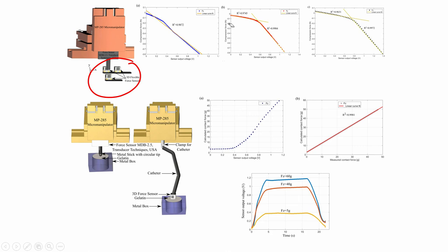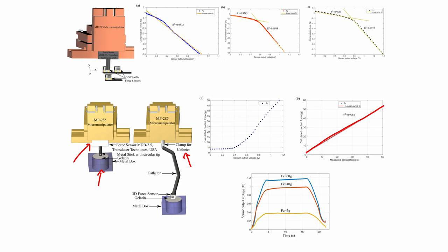Instead of measuring resistance directly, a potential divider or Wheatstone bridge gives the voltage change. Applying a known force reveals the output voltage, allowing calibration of the fabricated sensor. This is a very important experiment — whenever you fabricate any sensor you must calibrate it against a commercial sensor. For tissue testing, phantom tissue is used first: a gelatin-filled metal box acts as the phantom. Pressing the catheter onto the gelatin shows calculated contact force versus measured contact force, with an extremely linear sensor response — which is ideal.